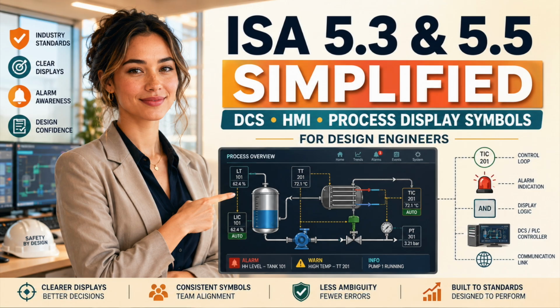A process vessel may be represented simply, but the process story cannot be simplified into something false. The symbol may omit construction detail, but the display must preserve the actual operating relationships, major flow paths, bypasses, recycles, utilities, and critical isolation arrangements. You can simplify the appearance. You cannot simplify the truth.